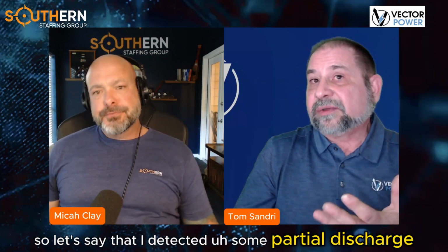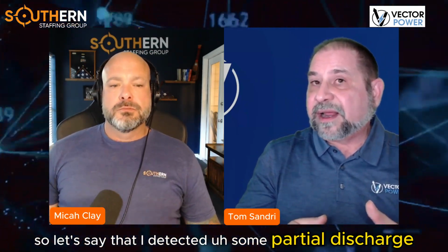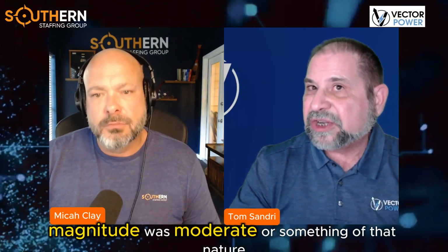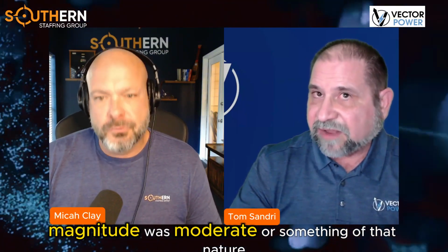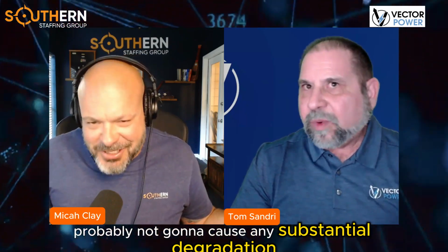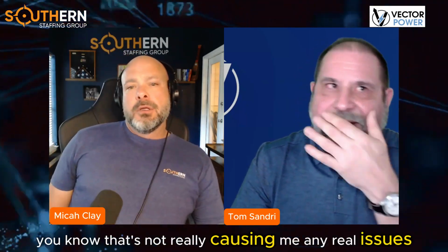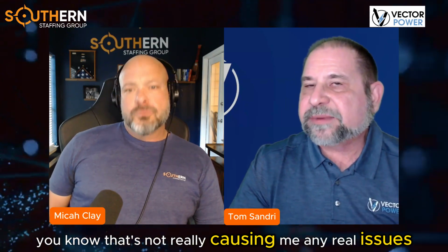Let's say I detected some partial discharge, but it was maybe at 2 times operating level. Pulse count was relatively low, magnitude was moderate, and it extinguished well before we got down to operating level. That's probably not going to cause substantial degradation to the cable, so I wouldn't see that as a real issue. I'll get years of good performance life out of it.